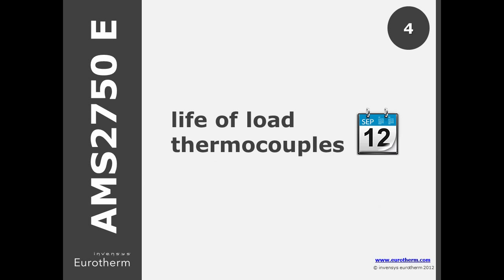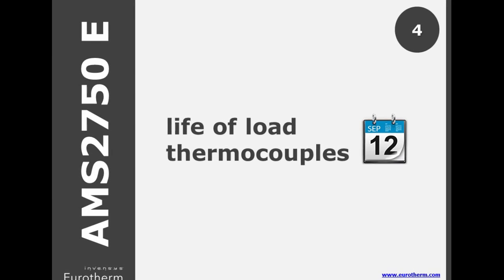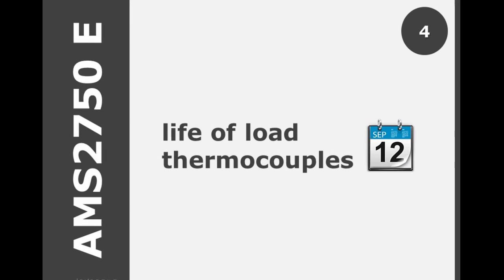For non-expendable load thermocouples, D prescribed how many days to use or maximum uses at temperature. In E, at 2200 to 2299 degrees Fahrenheit, a time period of 3 months has now been added, along with the 10 uses as specified in D.